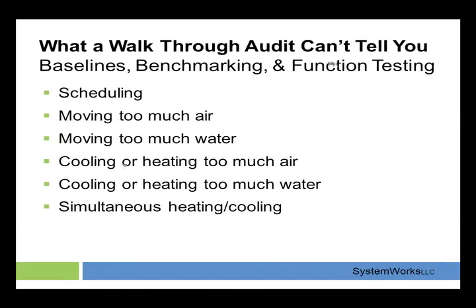Moving too much air. Gosh, every time we go out to a job, especially in the past, oftentimes the equipment was oversized. It was decided for a design degree day, and it may be moving 15 to 20% too much air. When you slow those fans down and get them to provide the correct amount of air, again, you're saving energy. The example we looked at with the pumps, they were pumping too much water, so they restricted the valves. Anytime you do that, you are wasting energy. So opening those valves, putting the pumps on a VFD, slows the pumps down, saves energy.